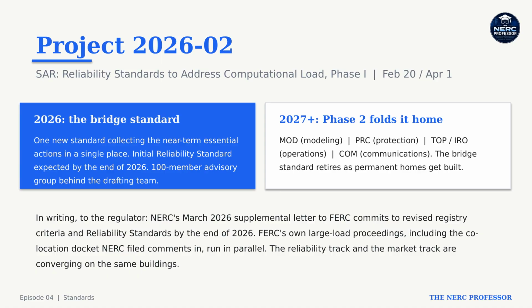The standards piece is Project 2026-02. The SAR is titled Reliability Standards to Address Computational Load, Phase 1. It went in on February 20th and posted April 1st. The plan: one bridge standard collecting the essential actions in a single place, fast. NERC expects an initial standard by the end of 2026.